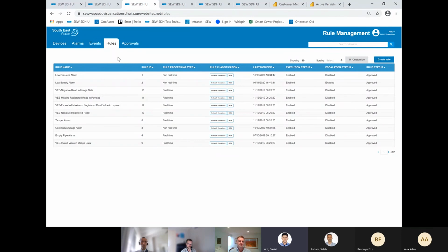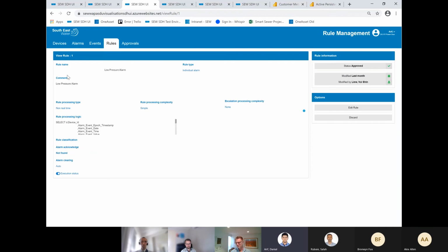So now we could have a rule set up. Let's say we've got this one, for instance. Whenever we set up new meters, and this is, again, when you've got a population that's going to span to hundreds of thousands of meters, you probably need a rules engine to manage some of the events that you think might be causing you a bit of a nuisance. So let's say when we install new meters, a low pressure alarm or a high pressure alarm gets triggered. You've got a new meter installed, there was no rolling average for it, so anything that it sees now triggers a high pressure alarm.